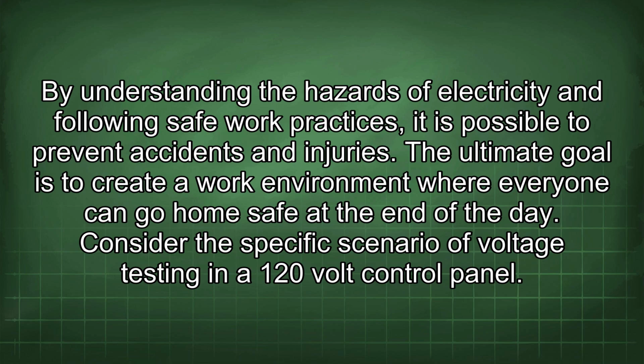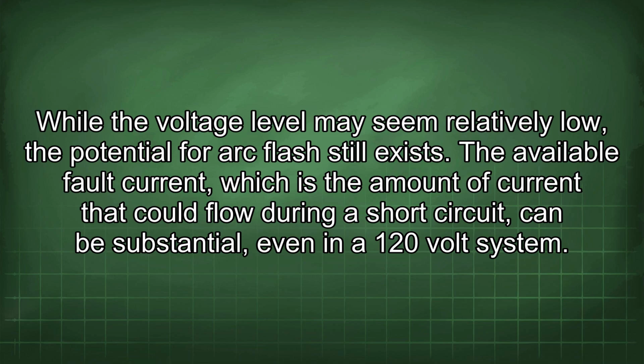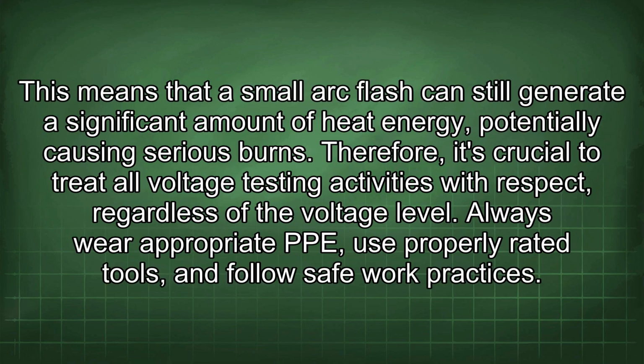Consider the specific scenario of voltage testing in a 120-volt control panel. While the voltage level may seem relatively low, the potential for arc flash still exists. The available fault current, which is the amount of current that could flow during a short circuit, can be substantial even in a 120-volt system. This means that a small arc flash can still generate a significant amount of heat energy, potentially causing serious burns. Therefore, it's crucial to treat all voltage testing activities with respect, regardless of the voltage level.